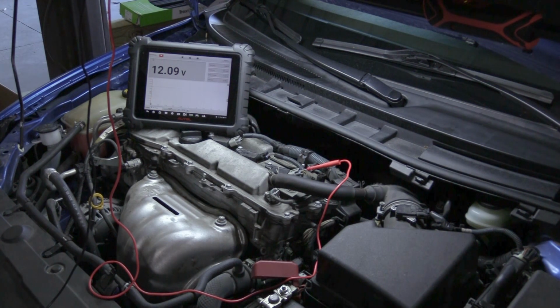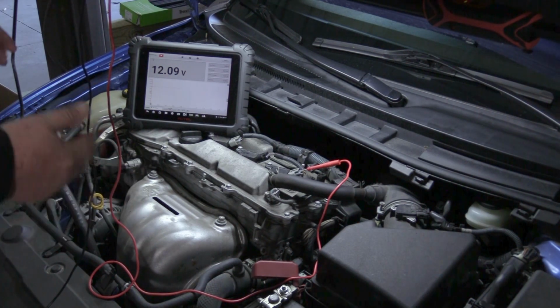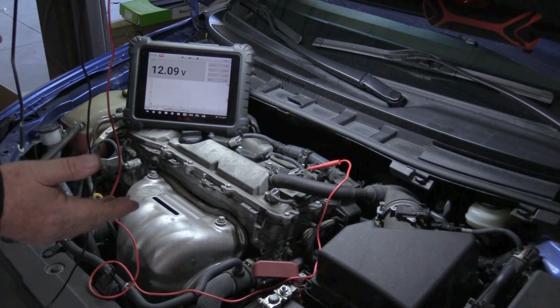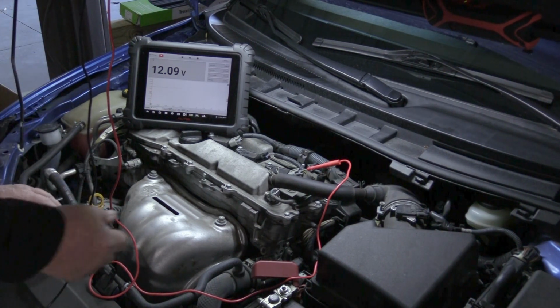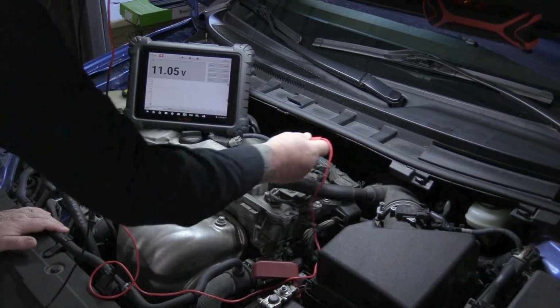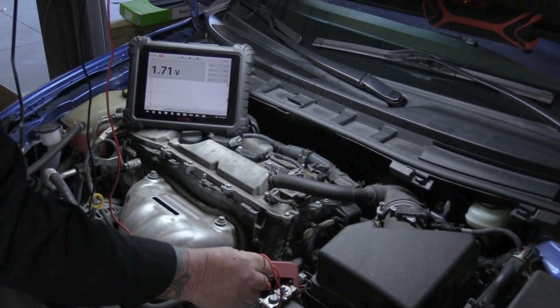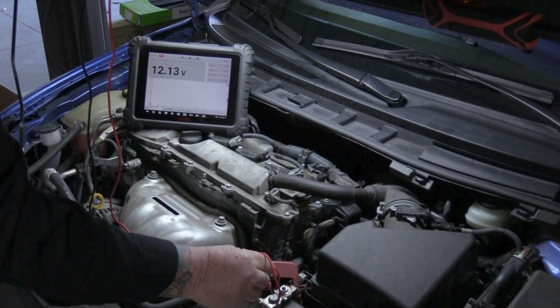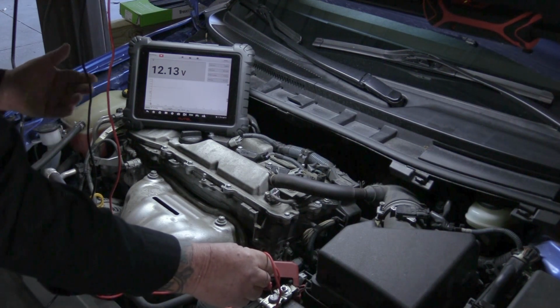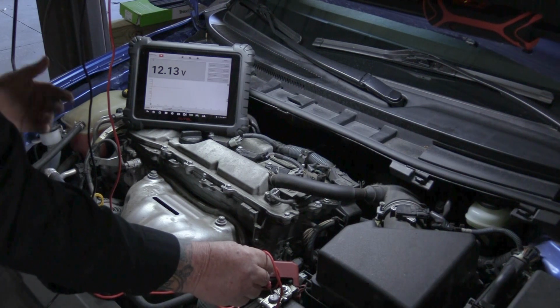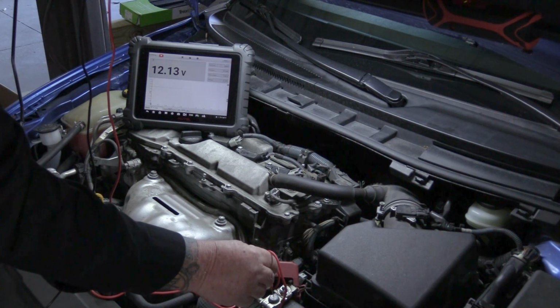I want to see if there's any voltage drop in the circuit, anything that might be causing an issue. I can do that easily here by measuring at the battery, and then again here, and subtracting the difference. For example, if we look here, we got 12.09, and if I touch the battery positive post, we got 12.13. So that's telling me there's 0.04 volts, or 40 millivolts, of voltage drop in that circuit.